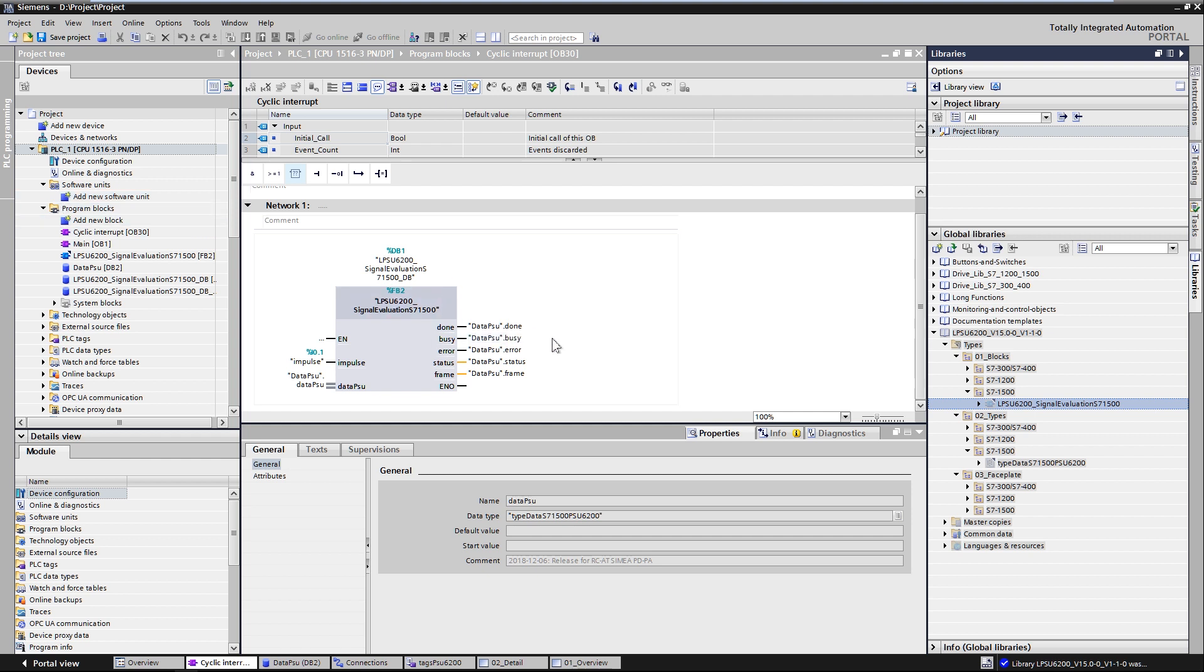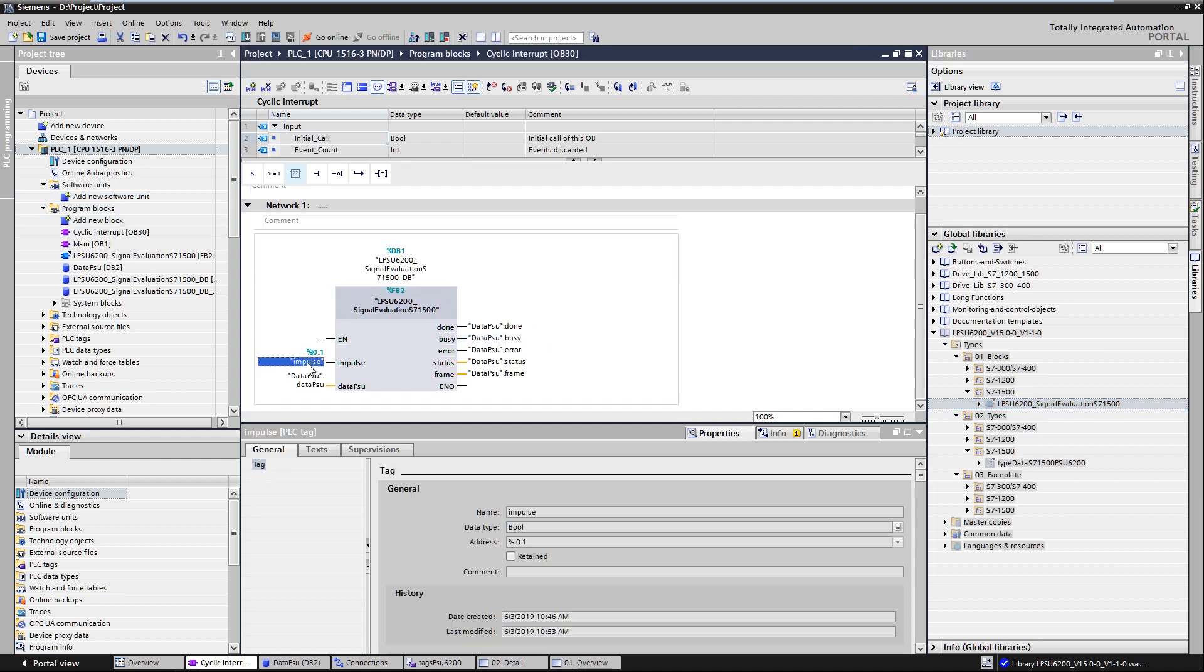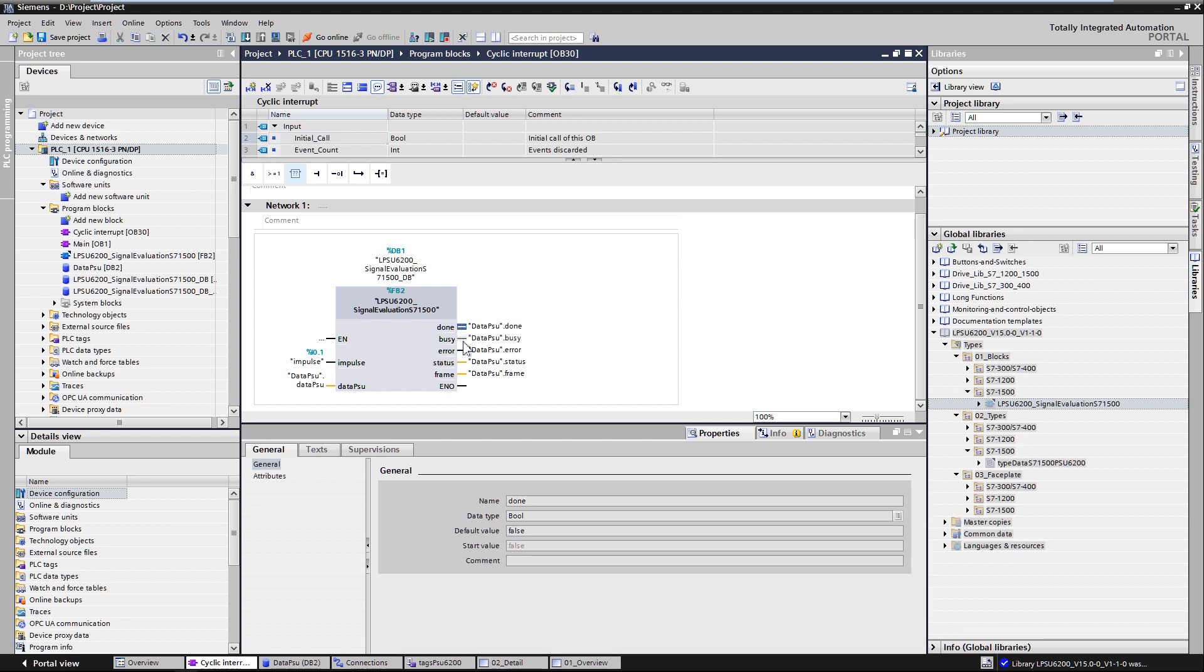The function block has the input parameter impulse. This is the input in which you need to read the coded signal of the PSU6200 at the input of the digital input module of your controller. The output parameters provide information about the current state of the block.